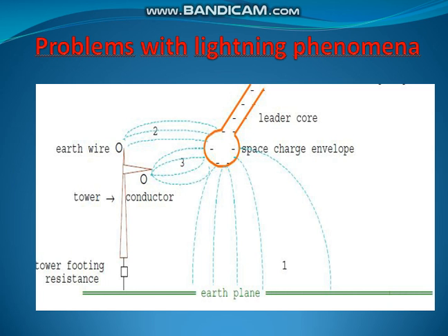The third mode of discharge is between the leader core and the phase conductor. This discharges the capacitance between these two and injects the main discharge current into the phase conductor, so developing a surge impedance voltage across the insulator string. At relatively low current, the insulation strength is exceeded and the discharge path is completed to the earth via the tower. This is the shielding failure, or direct stroke to the phase conductor. The protection of structures and equipment from the last mode of discharge by the application of lightning conductors and earth wires is one of the oldest aspects of lightning investigation, and continues to be so.